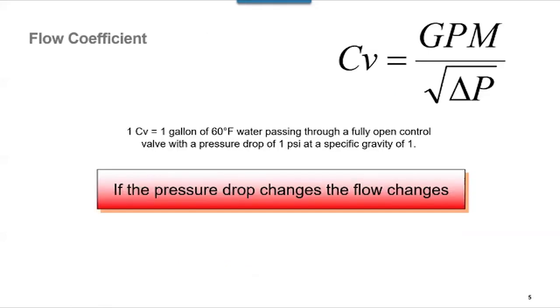Now, to fully understand how pressure affects the output of the control valve, let's work our way back a little bit and talk about pressure dependent control valves. We know that flow coefficient is the sizing relationship between flow and differential pressure across the fully open control valve. And keep in mind, this is a shortened formula. We know there's a specific gravity constant that should be plugged in there, but since we're looking at water or water with glycol, typically we're going to be at 1 or very near 1, so that really doesn't affect our calculation that much.